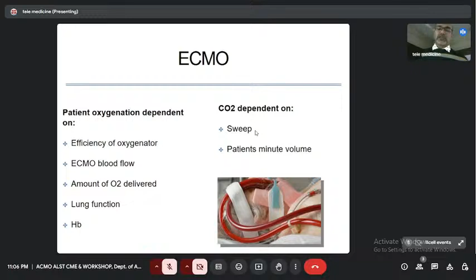For the sweep, we use 2 to 3 liters of oxygen coming into the oxygenator, and that takes the CO2 out. But oxygenation depends on the efficiency of the oxygenator plus the amount of blood flow actually going into the machine. So it's very flow dependent.